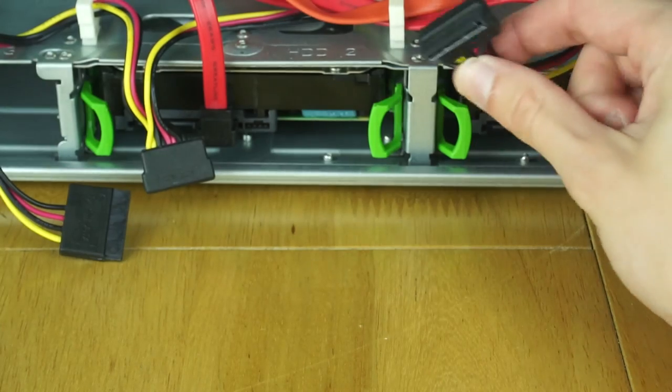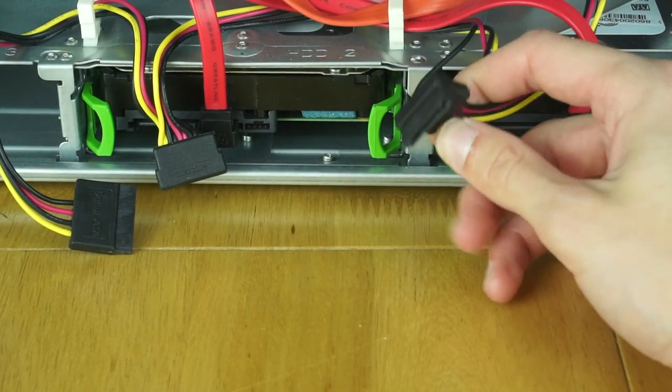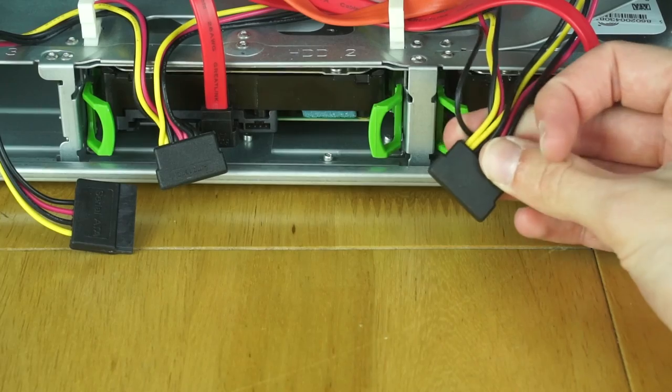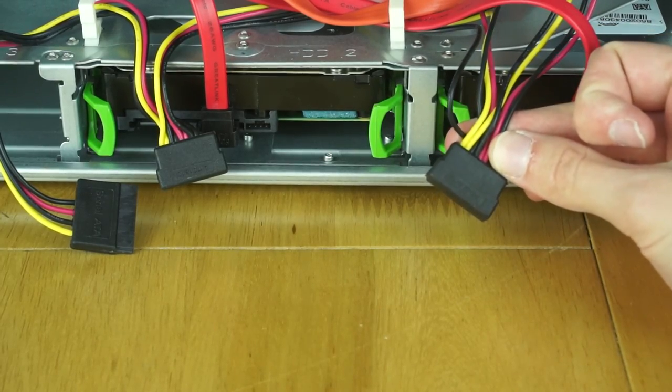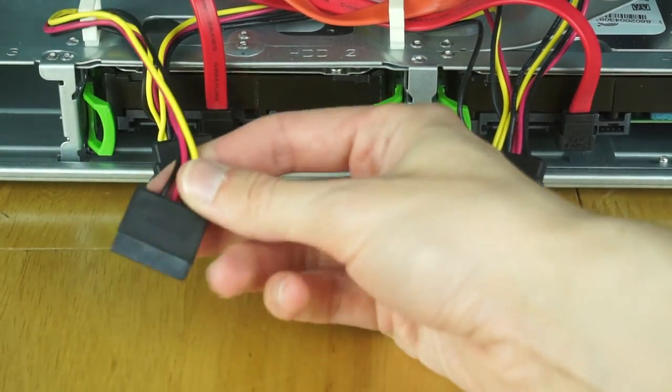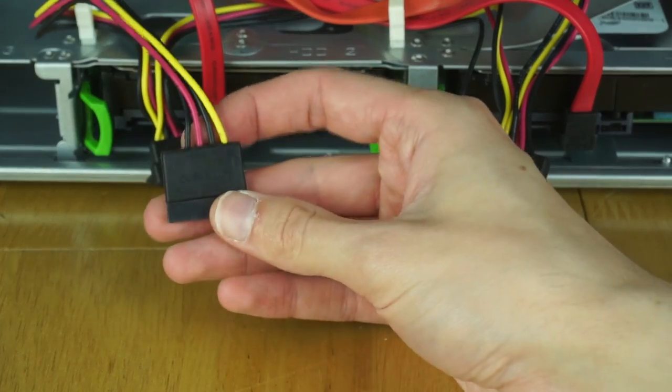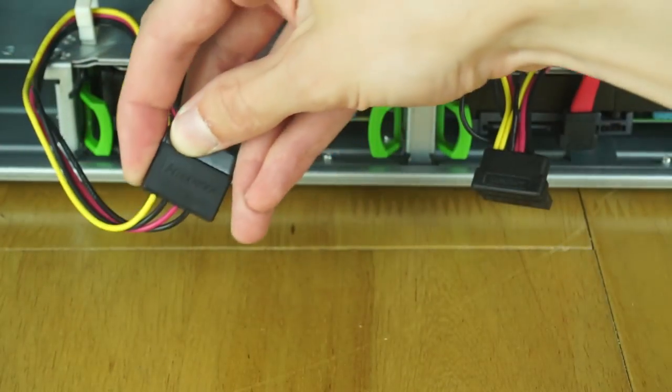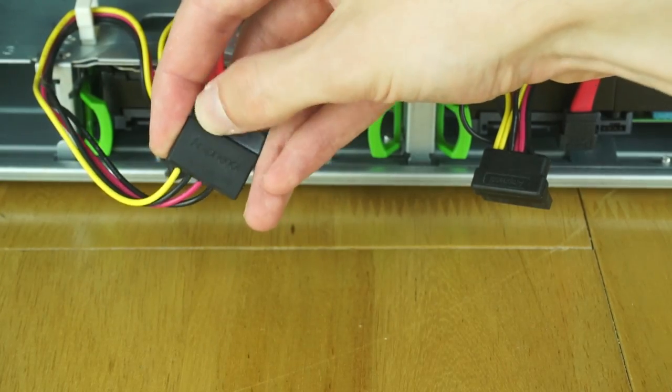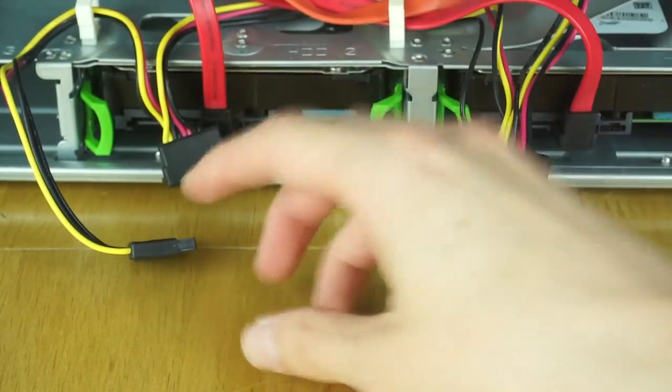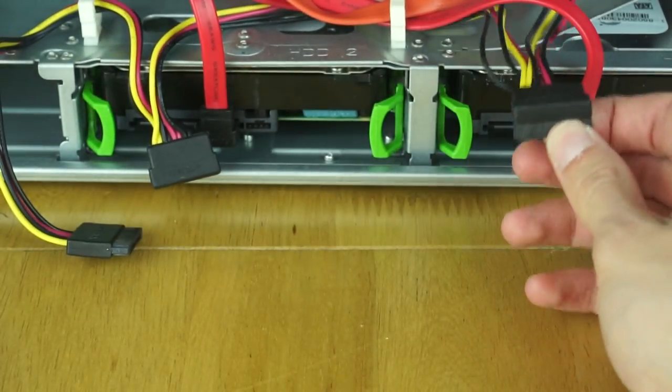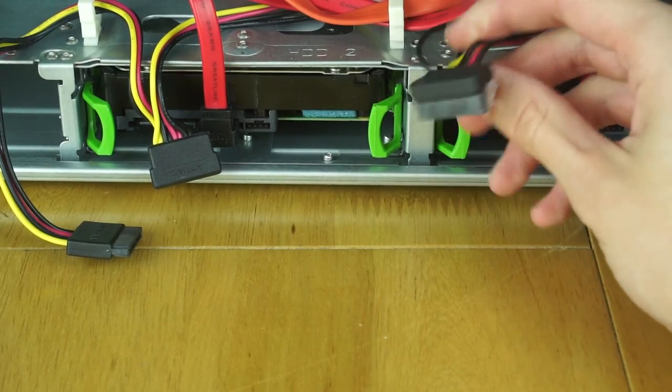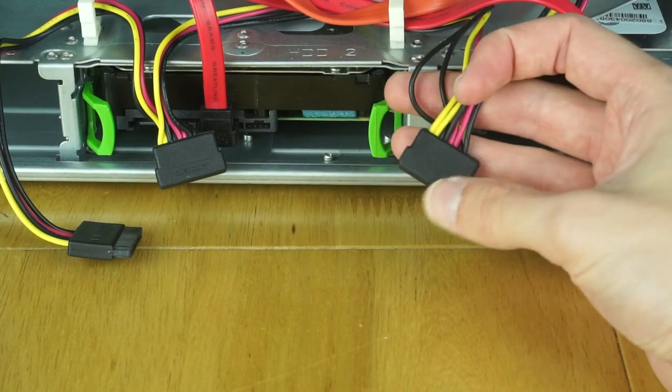I've not seen any of this sort of right angled type melt or catch fire before, but they're probably a much less common type. I've never seen these outside of this machine. However, this is the type here that I've seen many of them catch fire, or people reporting them anyway. Including these Amphenol branded ones, that brand has had many reports of these catching fire. So, these are all Amphenol branded, and even though these are the right angled ones that I haven't seen before, I just don't trust them, and I don't want them in the machine.